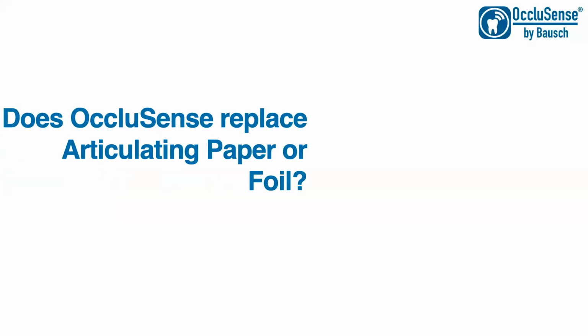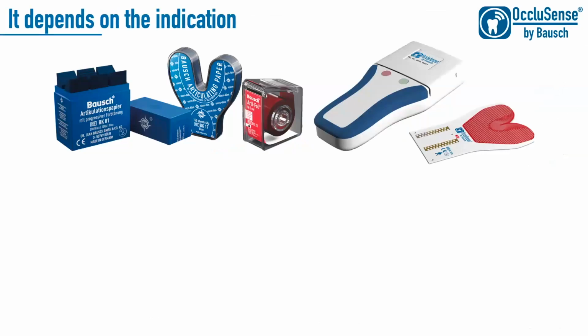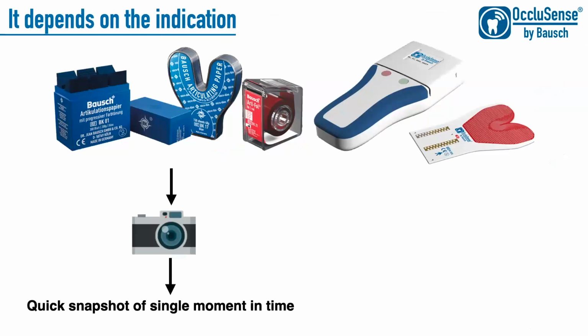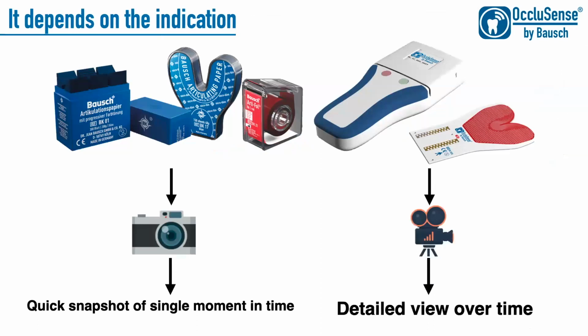Okay, so maybe the most relevant question for you now, can articulating paper be replaced by OccluSense? I would say it depends on the indication. If you want to take a quick snapshot of a single moment in time, then you are good to use articulating papers. But if you want a detailed view of the three-dimensional occlusal processes over a period of time, and you want a video recording, you should grab your OccluSense.